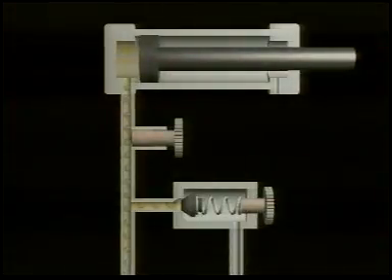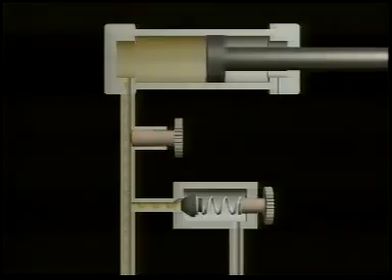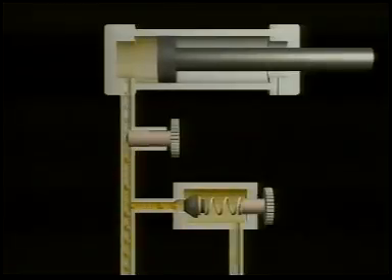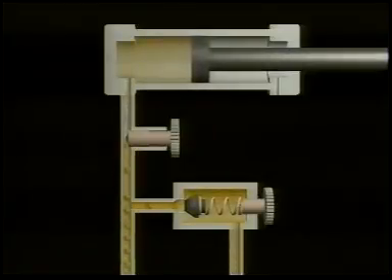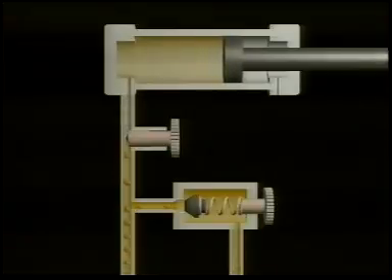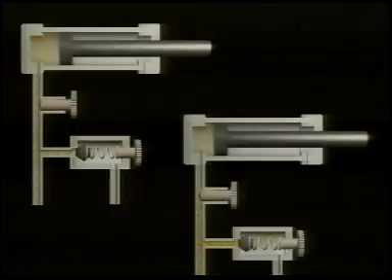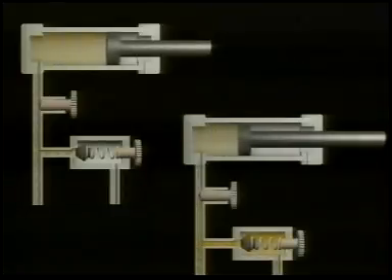Here we see the working speed of the cylinder with the flow control valve open. If the restrictor causes an increase in resistance, the pressure rises prior to this. The pressure relief valve begins to open, which causes the fluid flow to be divided. One part flows to the cylinder, the other back to the reservoir. The slower flow rate now in effect reduces the working speed.